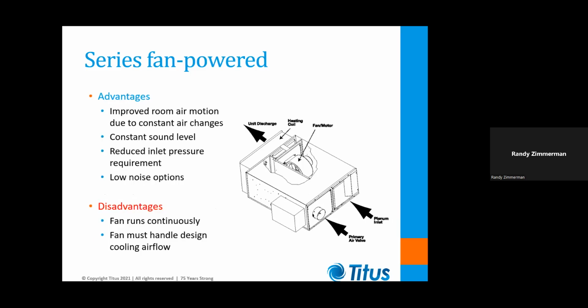So series boxes and parallel boxes each have their advantages and disadvantages. The advantages of the series fan-powered box would be that you get constant air motion in the room because you've got that constant discharge from the fan. That's going to give you more room air mixing, should make the space feel fresher because you're getting more air motion, more air changes. You're also getting a constant sound level from the fan. And many manufacturers of series fan boxes offer noise reduction packages to reduce the sound level of that fan. You've also got the reduced inlet pressure we discussed earlier.